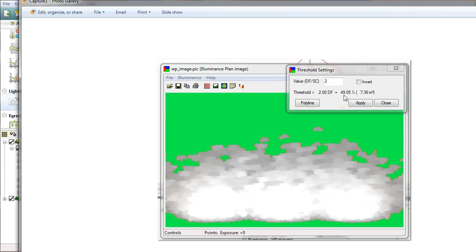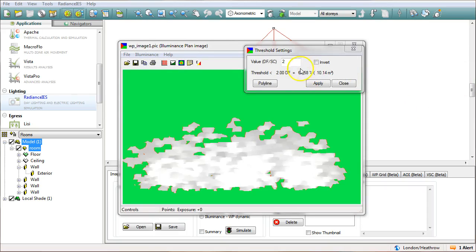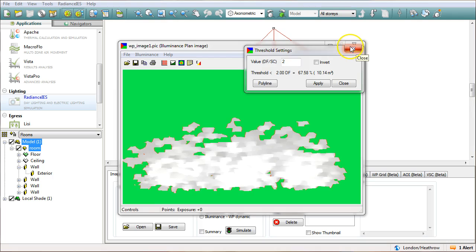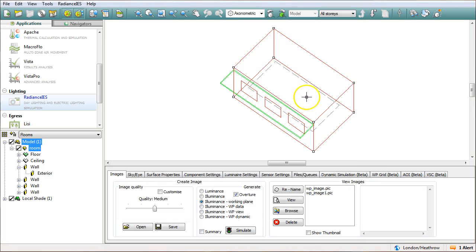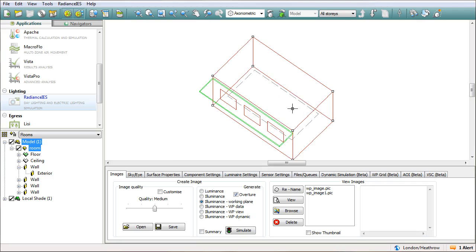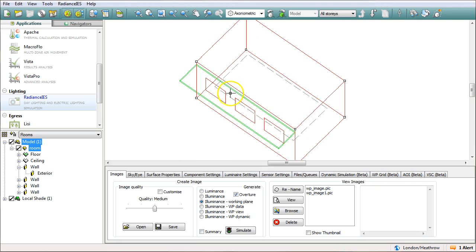so by putting that canopy on there we've done two things: we've reduced the air temperature in the room because it's stopping solar gain or reducing solar gain but we've also had the effect of making the room slightly darker. More of the room has a daylight factor of less than two, it was 49 percent of the floor area was less than two at the start of this simulation, it's now gone up to almost 68 percent because we've put the canopy on there. So we've got positives and negatives: the canopy will help to reduce solar gain which will have the effect of cooling your room but it has the negative effect of making your room darker. Okay so both maybe are obvious conclusions that you would draw before even running the IES package but this is just a walkthrough on how you can prove those points using the software.